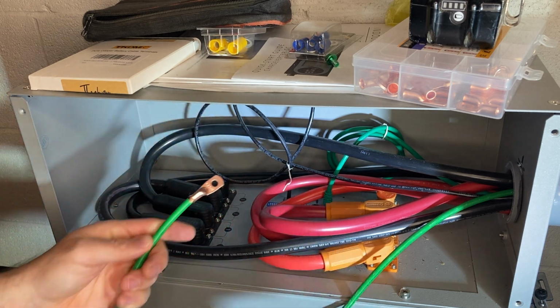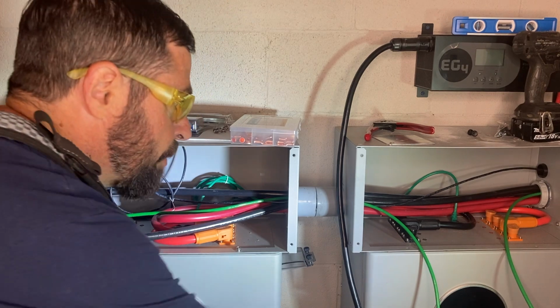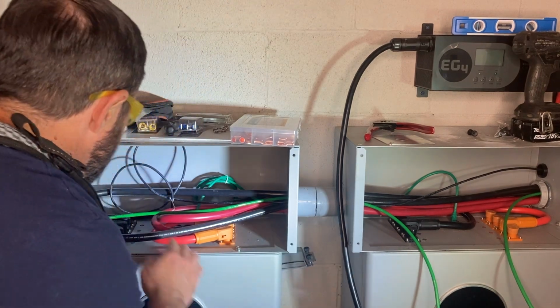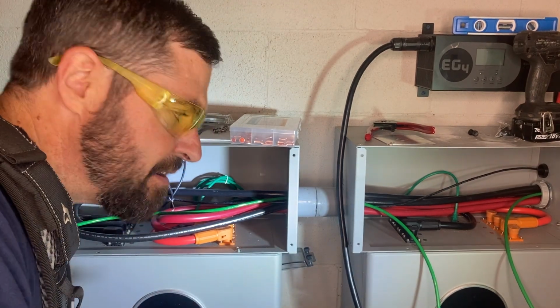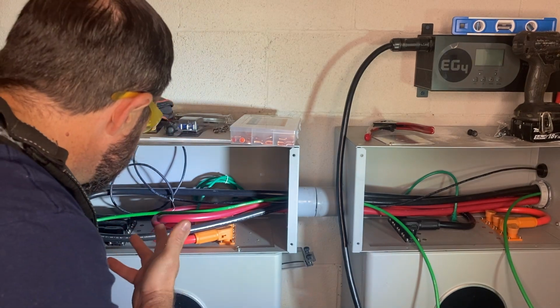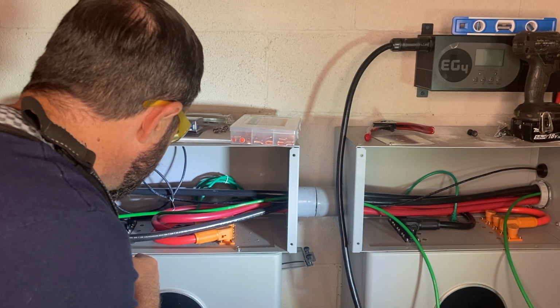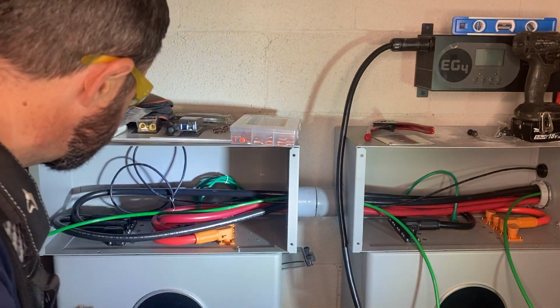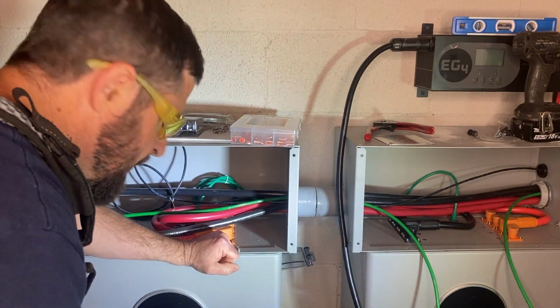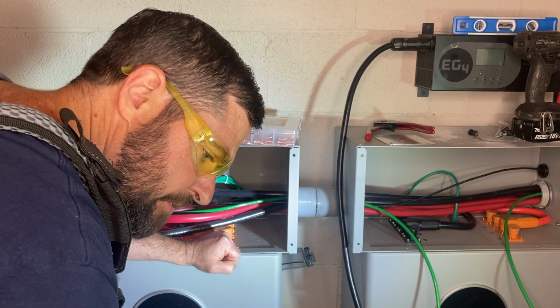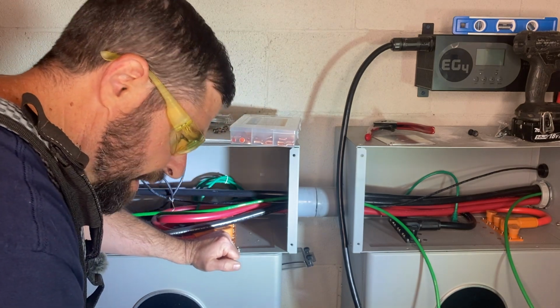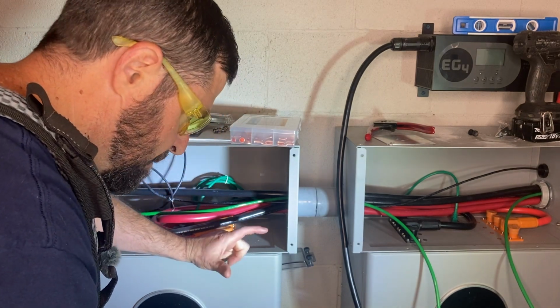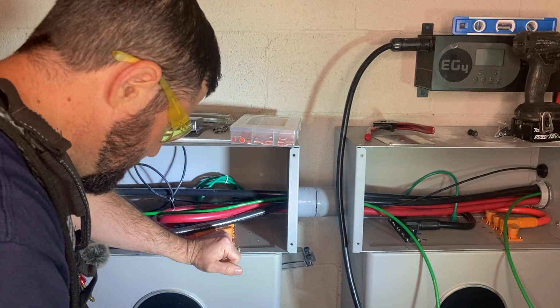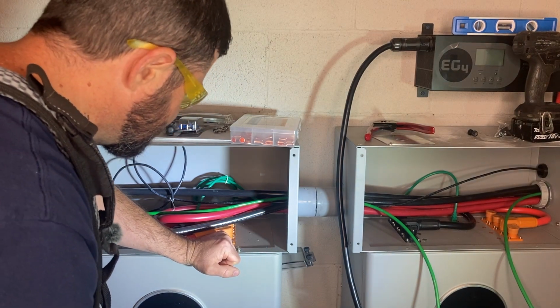Alright, so I'm going to go ahead and ground the batteries. Now, they've got the little ground screws back there in the back, but the instruction manual tells you to run a little jumper over there from the conduit box. To my knowledge, you can't land a bunch of different ground terminals on the same screw. You can on a ground block or a ground bar. I don't really want to install a ground bar here, I don't think it's necessary.